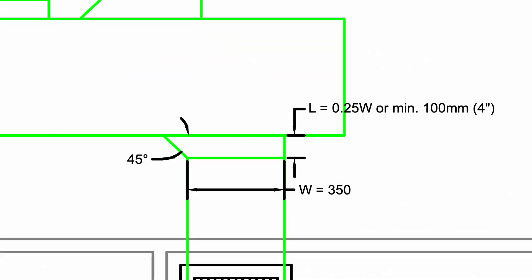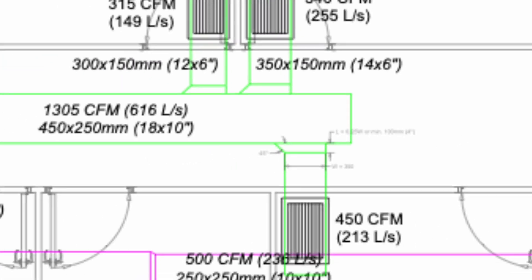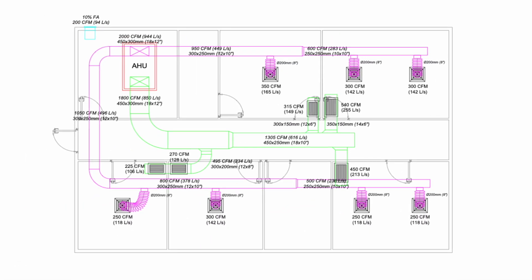For the branch duct that tees off the main duct, we can use a 45 degree entry fitting. According to SMACNA, the entry angle should be 45 degrees and the length of the fitting should be a quarter of the branch duct width or minimum 4 inches. Once we have done with the return duct, we want to add dampers to this location.